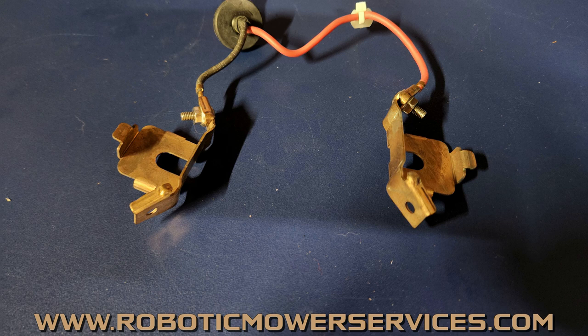And see if you have high resistance, just see if that makes a change in it. If not, then definitely you've got to replace that whole component. But it's worth a shot to take the time to clean that stuff up and see if that's where your problem's at, because you don't want to go throwing new parts in there and then next thing you know, a couple months later, you're having the same issue, because this is an environment where it's going to attract a lot of moisture and you're going to have these corrosion issues over and over again.